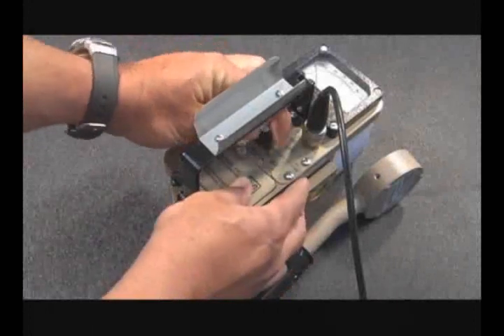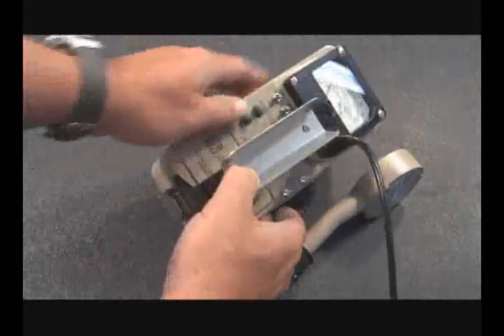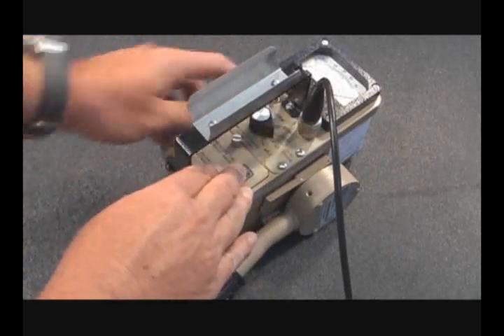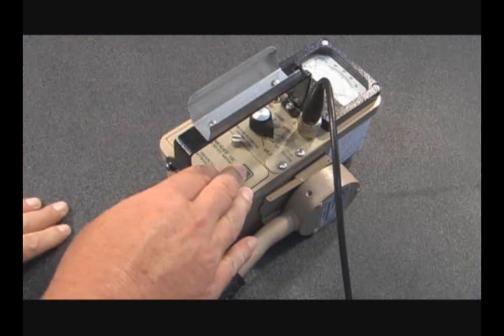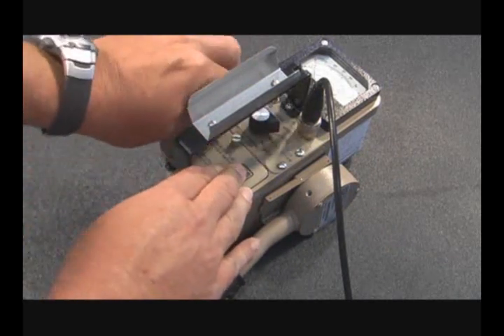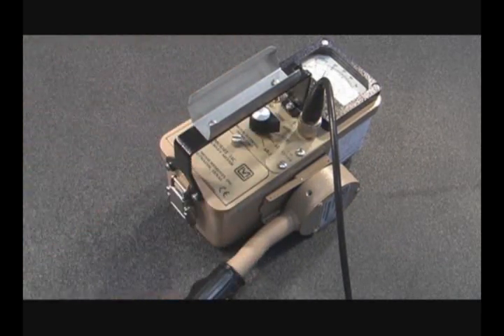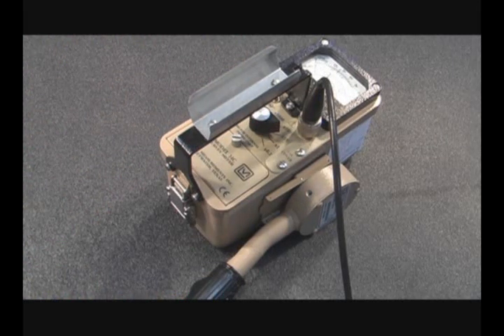Turn the range selector switch to the times 0.1 position. Turn the fast-slow toggle switch to fast. Expose the Model 44-9 detector to the check source mounted on the side of the Model 14C. Rotate the range switch through the lower scales until a meter reading is indicated. The reading should be within 20% of the initial reading taken during calibration. This reading can be found on the calibration certificate sent with your response kit or on the calibration sticker on the side of the instrument.